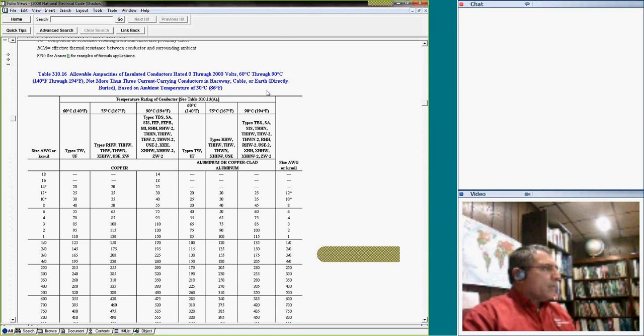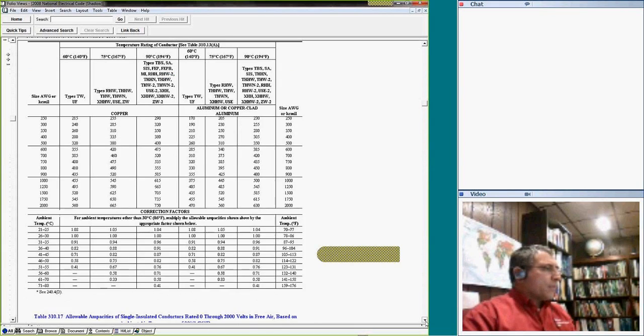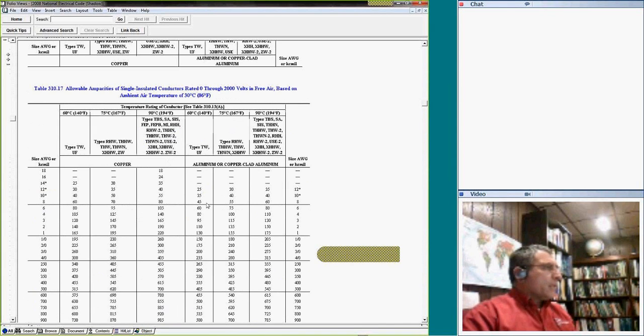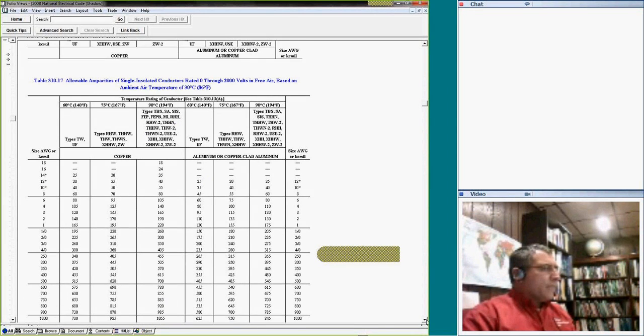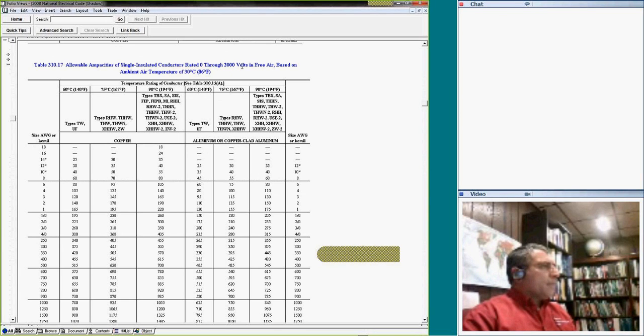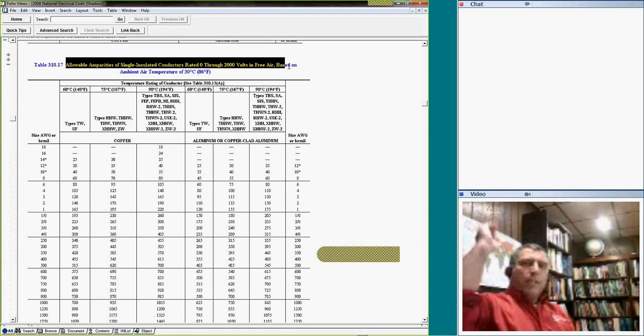Directly buried conductors also apply far away from other conductors. Now look at 310-17. 310-17 is the table for conductors in free air, based on an ambient temperature of 30 degrees. This is the allowable ampacity of single insulated conductors in free air, based on ambient temperature. So you have conductor and insulation.